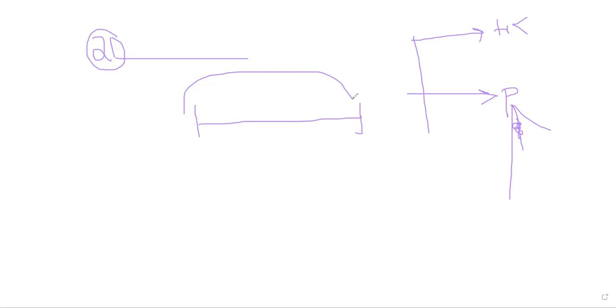That is a differential protection, generally how it works. But I have not done it for any project. Mostly we use distance protection because all the line lengths are more than 20, 30 or 40 kilometers. So coming to distance protection, we have to talk about the zones of protection: Zone 1, Zone 2, Zone 3, and Zone 4, which is a reverse zone. Fine. Zone 1, Zone 2, Zone 3.